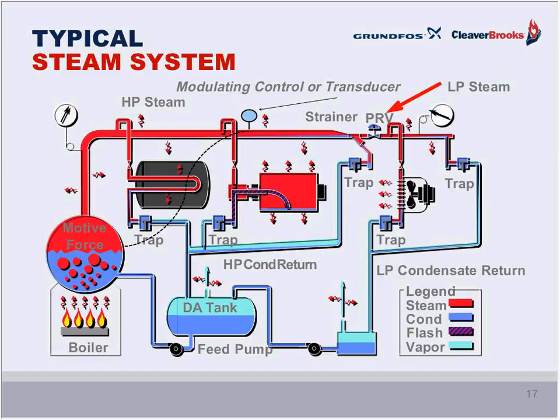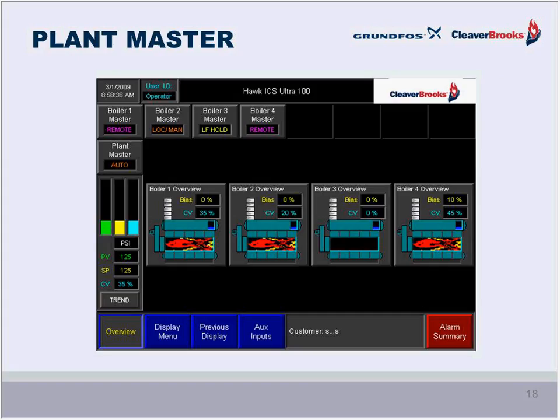Or the modulating control, rather than being mounted on the boiler, could be mounted in the steam header as shown here, giving a more anticipated signal of what is going on in the process. Or maybe this is a transducer sending a 4 to 20 milliamp signal. And that could be going to a plant master, which is controlling several boilers required to meet a rather large load or maybe a large varying load.